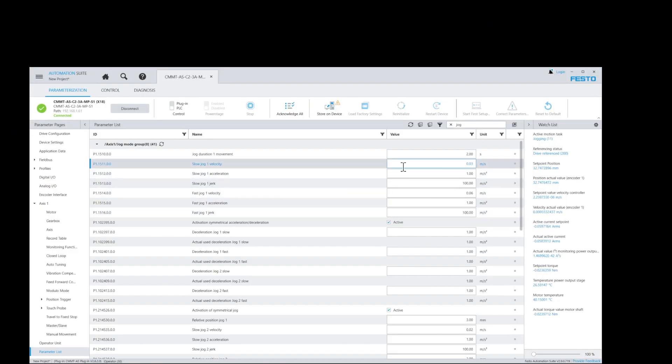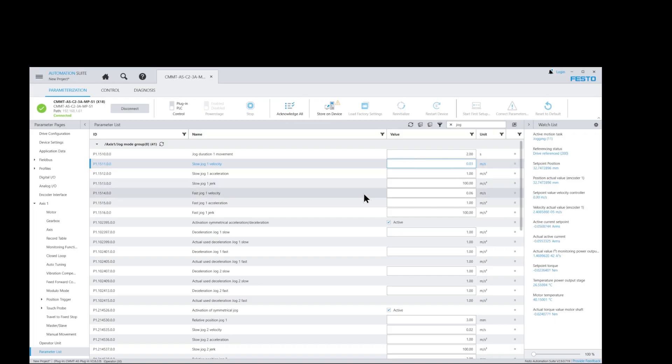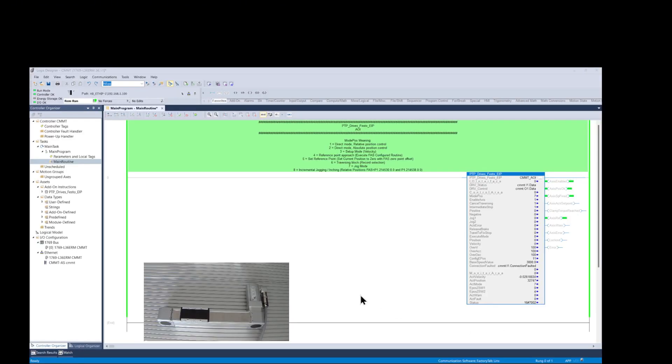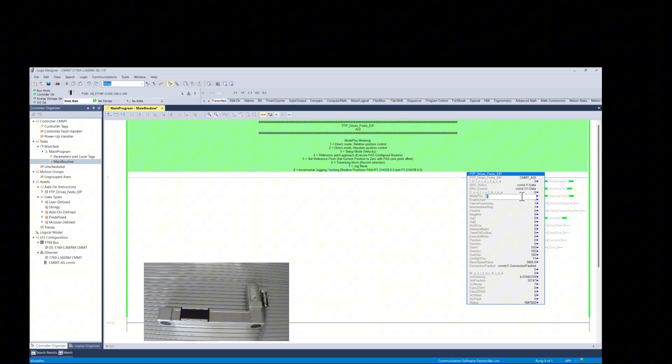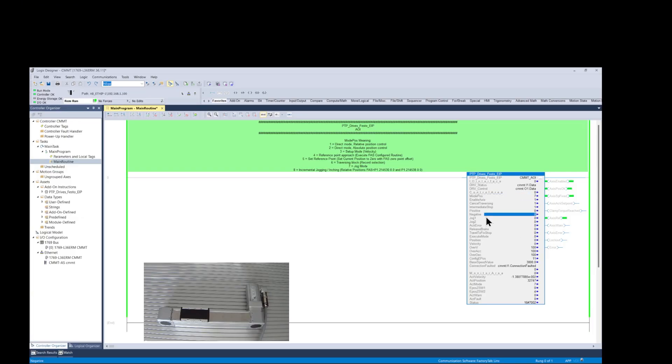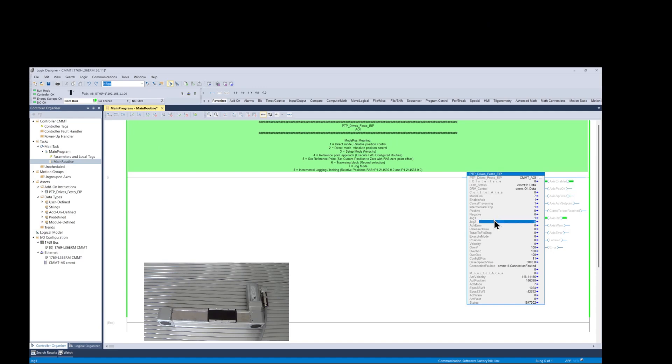To initiate a jog move, the velocity and the position field values don't matter. The jog speeds are set inside the FAS software. Let's begin by changing the ModePos value to 7. And to begin a jog move, we have to set to 1 the jog 1 value for positive motion, and also set to 1 the jog 2 for negative motion.